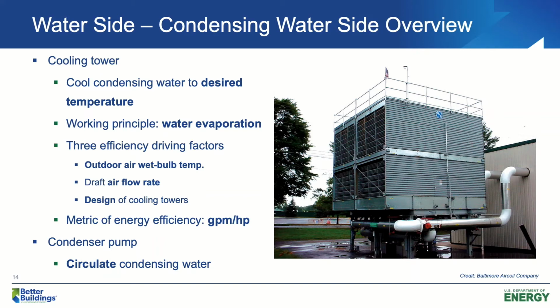Similar to chiller primary pumps, we have condensing water pumps to overcome the elevation of cooling towers and circulate condensing water through the cooling towers and reject the heat for chillers.